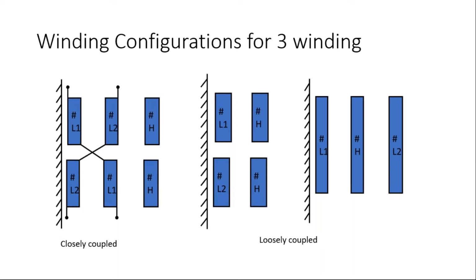Now, what is closely coupled? Closely coupled is where the impedance between the two secondary windings is much less than the overall impedance. And the construction is shown here, where the low voltage winding is in a crisscross configuration. Then we have another configuration that is mainly for loosely coupled. So these are the configurations which Bala described here for closely and loosely coupled.